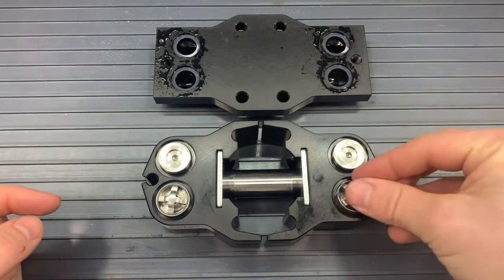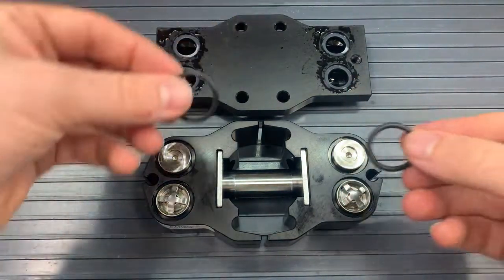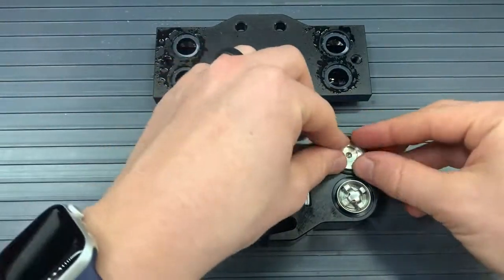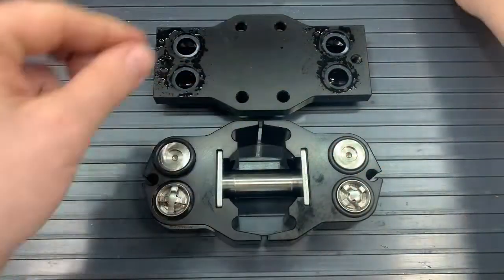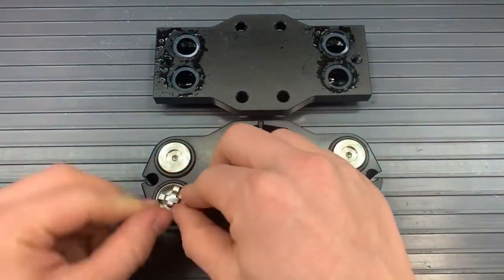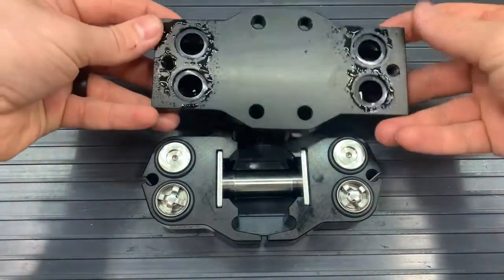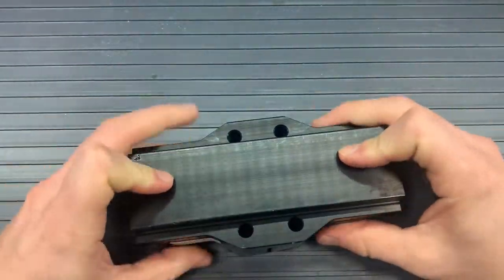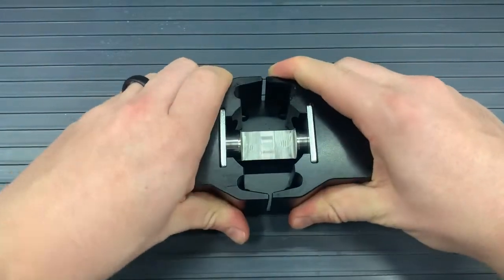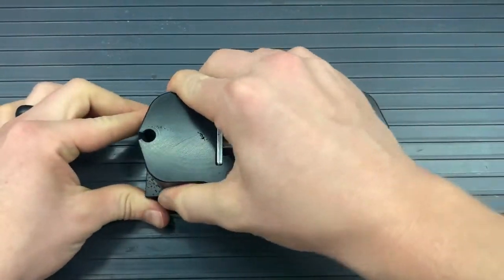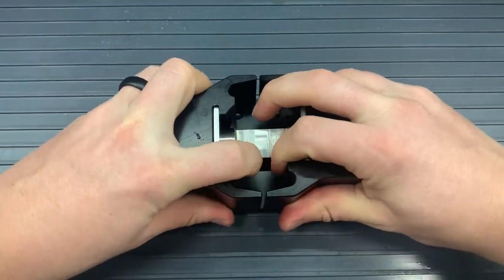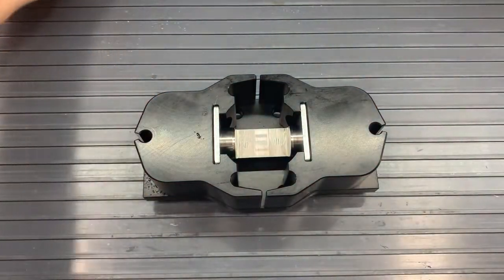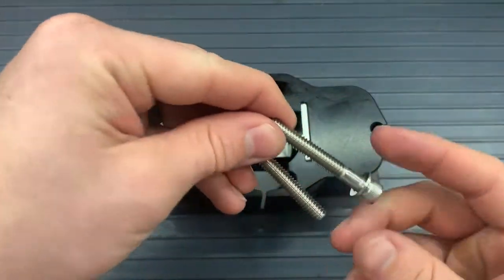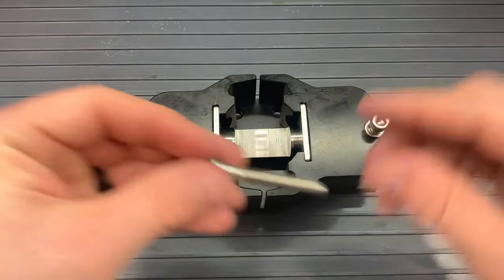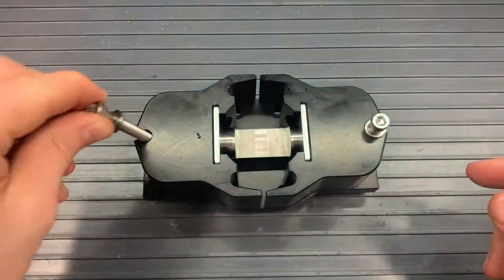The 116 O-ring from kit B will now go on each of these valves, and they should nestle up into that pocket of the head. We'll now flip over the manifold onto the pump heads, and we'll position it. We'll jiggle it around, maybe flip it over, move the pump heads back and forth so that there's a tight fit between the heads and the manifold. Now that we have our heads and our manifolds together, we want to lay the pump on the manifolds so we can put those bolts back on the pump. We will need the metal washers as well.